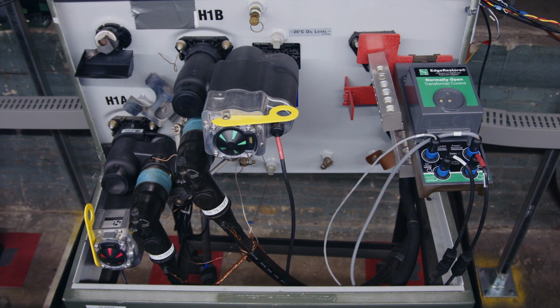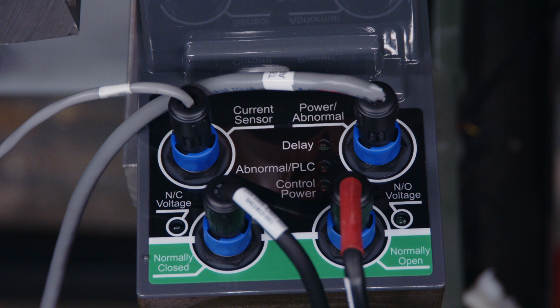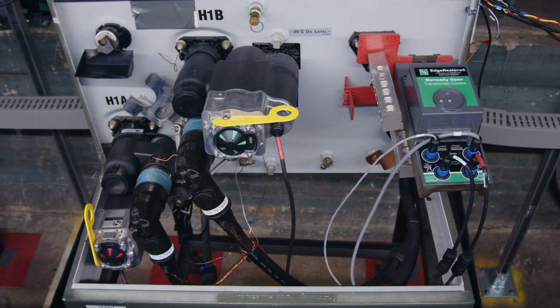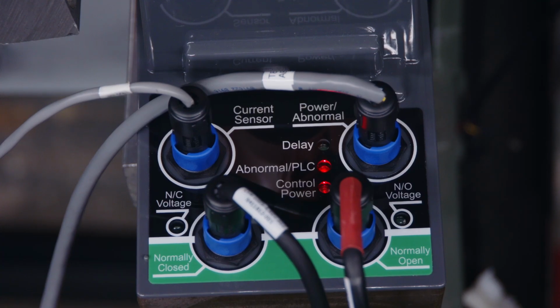For an EdgeRestore system with a normally open transformer, Step 1. Make sure the EdgeRestore system installation procedure has been completed. Step 2. Make sure the normally closed control cable is connected to the normally closed connector on the control. Step 3. Make sure the normally open control cable is connected to the normally open connector on the control. Step 4. Apply power to the control using the cordless power module. Step 5. Wait until the control power LED stops blinking.